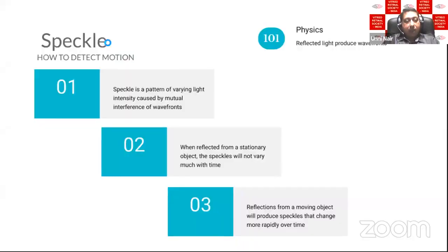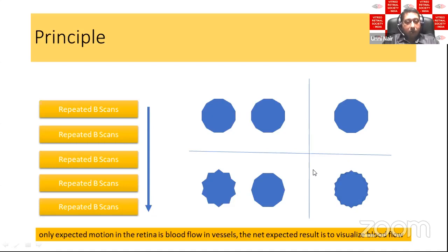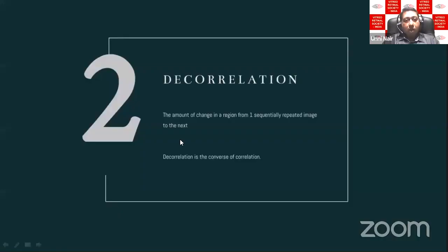There are four tenets of OCTA: the detection of a speckle, the scanning of a volume, understanding what decorrelation is, and viewing using en-face. A speckle is a wavefront produced by light. When a wavefront is reflected off a stationary object it doesn't vary, but when reflected off a moving object it produces a change called a speckle. In OCTA, repeated B-scans are done on a single point — any change indicates movement, and in the eye the only moving object is the red blood cell, thus blood vessels are visualized.